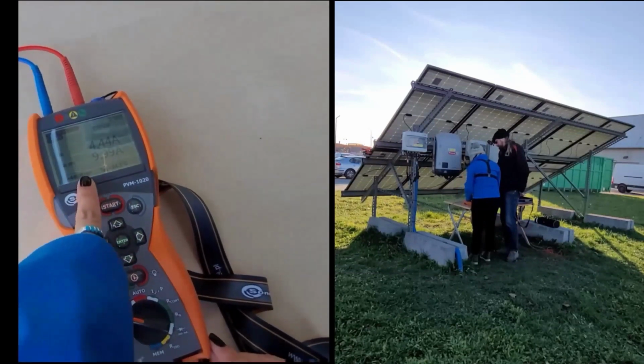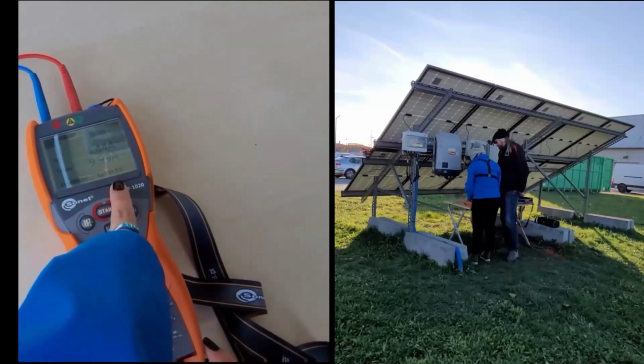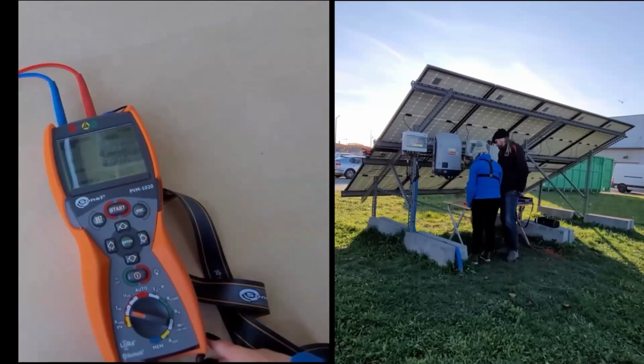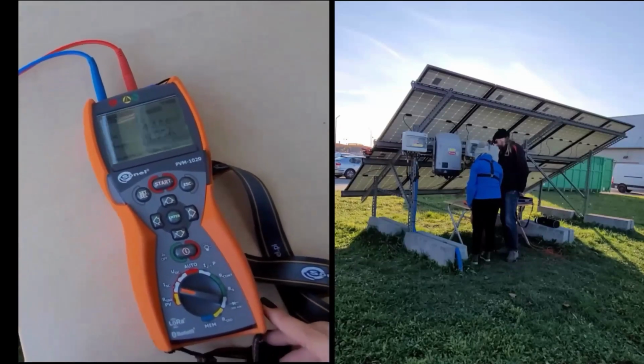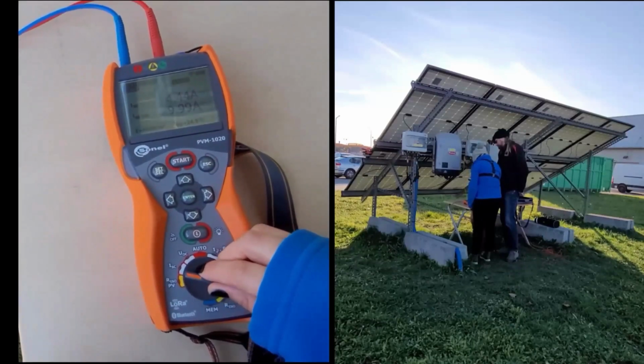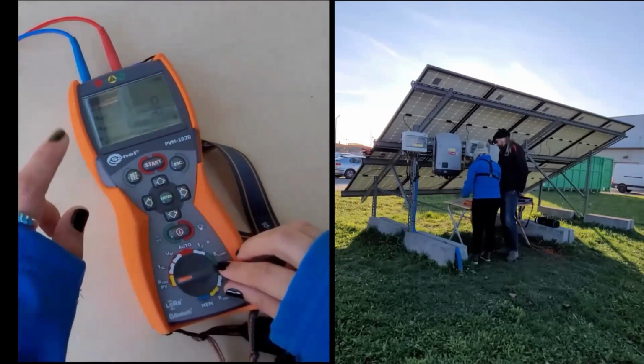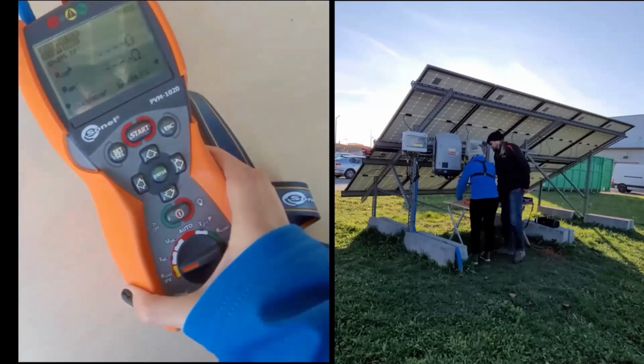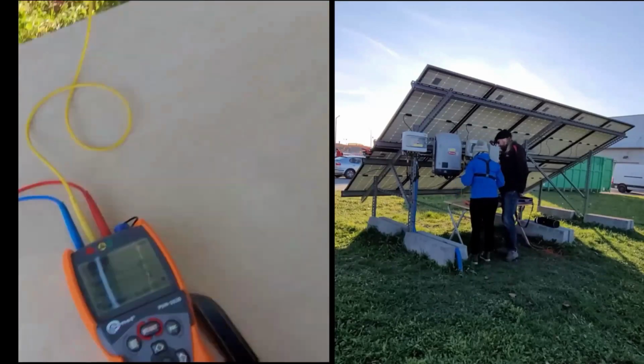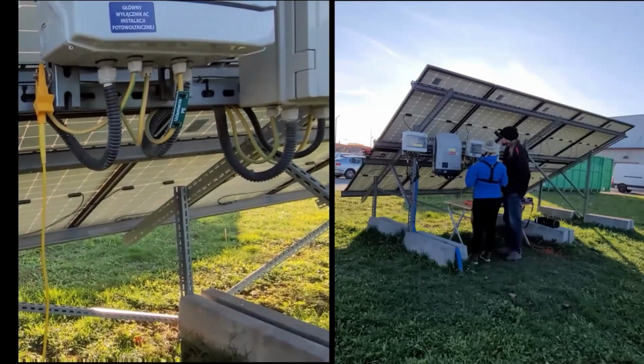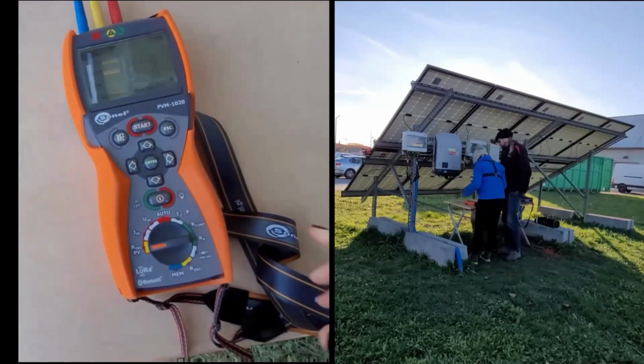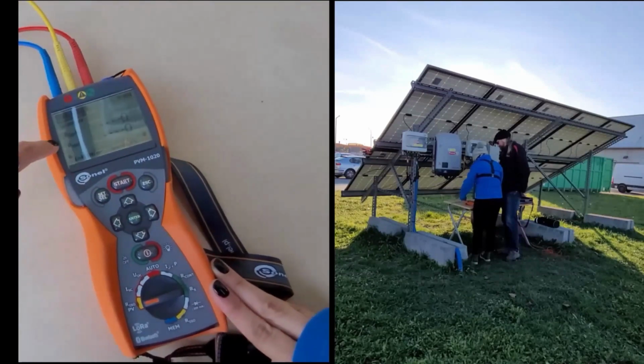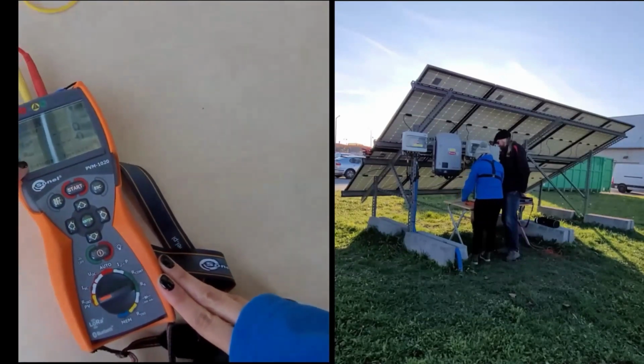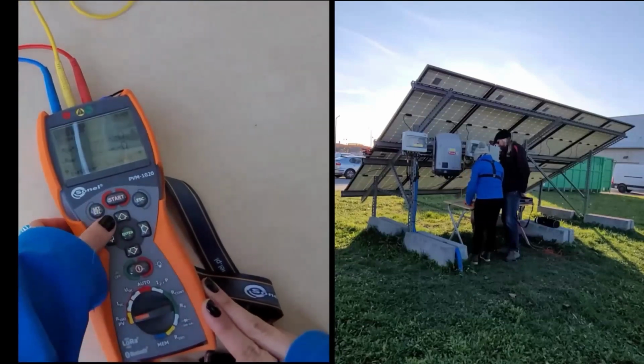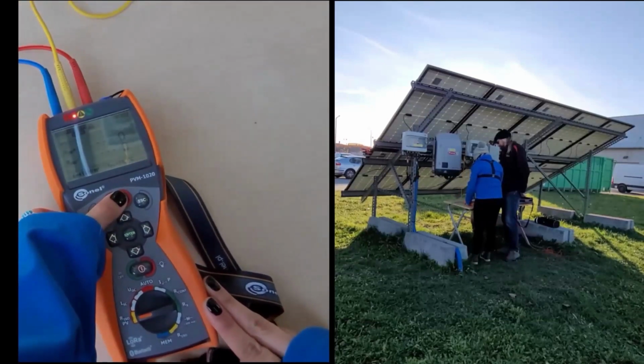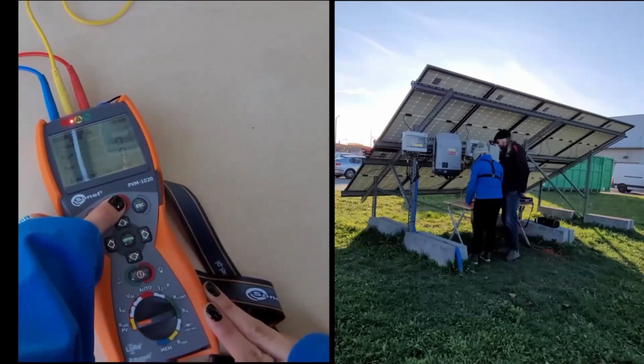Finally, we check the insulation resistance. Most methods do this in 2 steps, as I said before. This method does the same. First, the meter measures the resistance between the positive pole and ground, and then between negative. You see here we have ground, positive to ground, and then negative to ground. We have to wait for start. The measure starts.